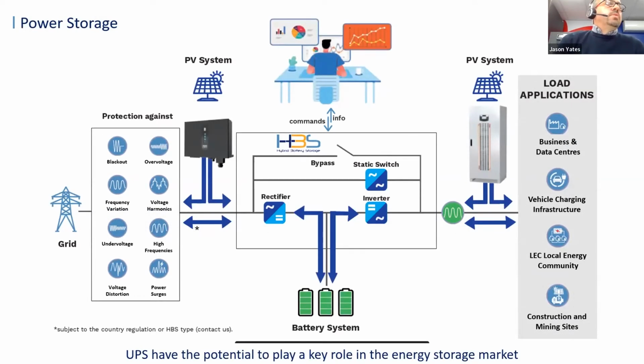This is a UPS system that's being used in conjunction with PV arrays, both on the input and on the output. It's still a UPS, so it still offers protection against the various issues on the electrical system in terms of blackouts, overvoltages, frequency variations, power surges, voltage distortion, and so on and so forth. But therefore, it can still be utilized to back up critical infrastructure. Basically, the way UPSs are going these days, UPSs are playing a bigger part and a key role in the energy storage market. And as more and more demand comes along for this, more and more developments are being made in the UPS sector.